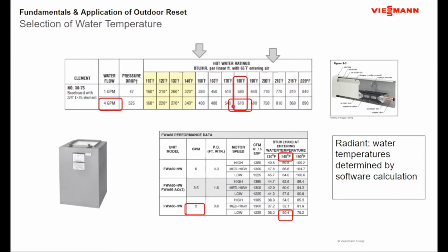for this baseboard. I could also design down at 150 degrees, and I'm getting about 400 BTUs per linear foot, about 2/3 the energy. So you can always select a different water temperature for design. It's just as the water temperature goes down, the amount of heat per linear foot for baseboard goes down. So if I have a target heat loss of the building, it means I need more heat emitter. Same thing happens when I look at air handlers.